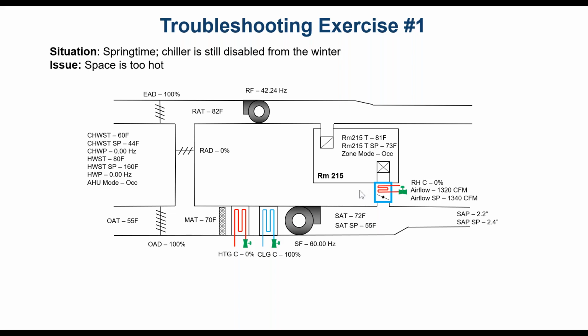Step 4.1, is the set point appropriate? Space temperature is at 81, set point is 73. I would say that set point is appropriate, yeah.